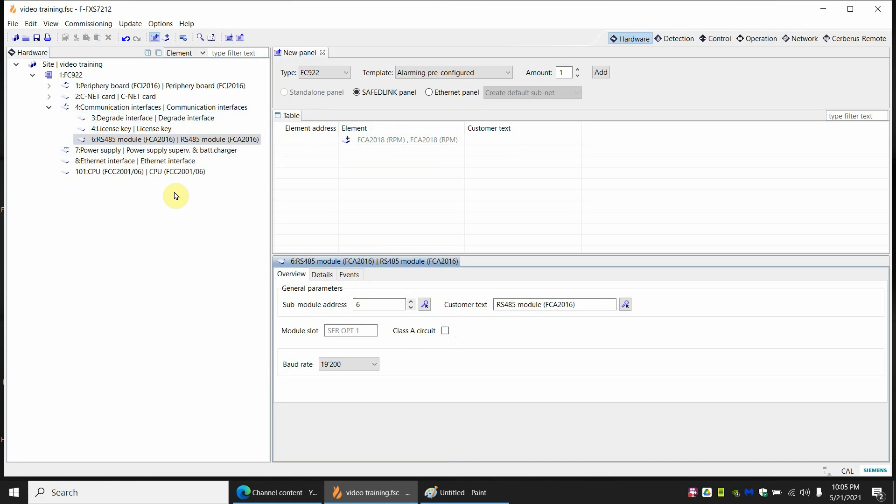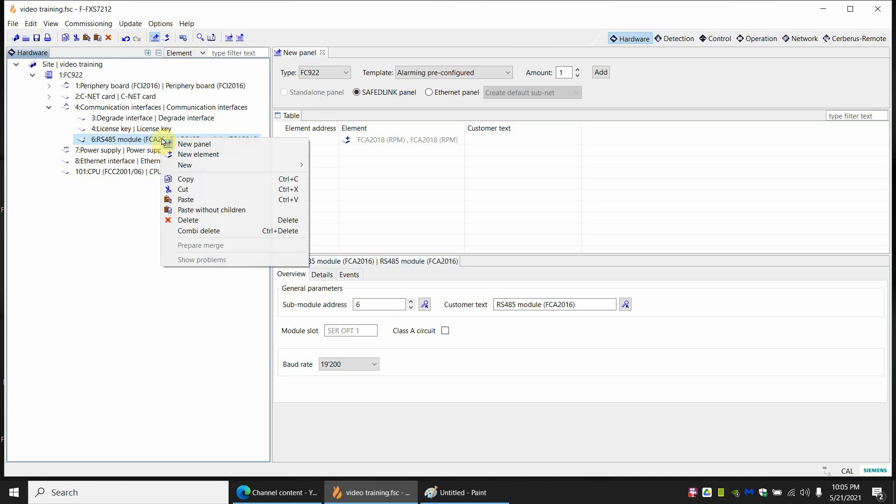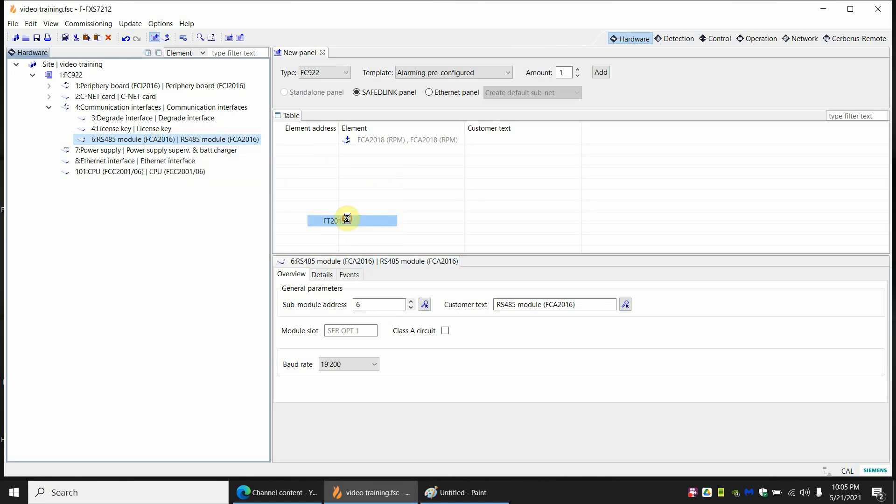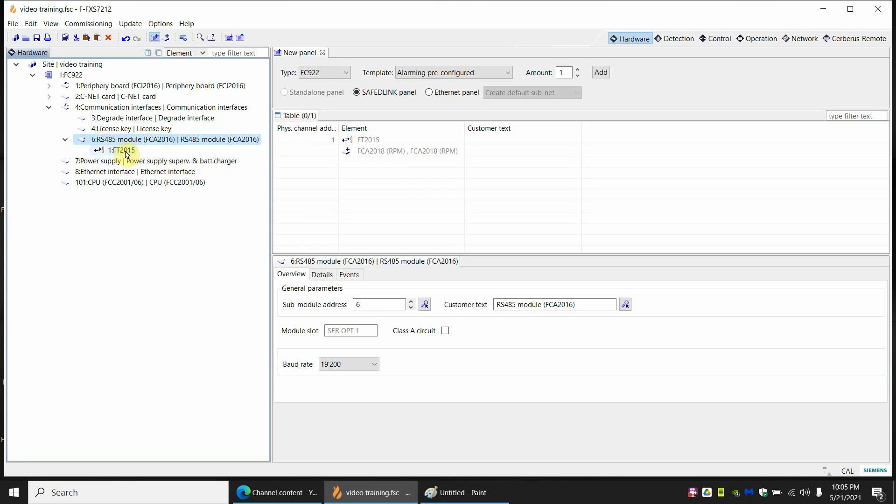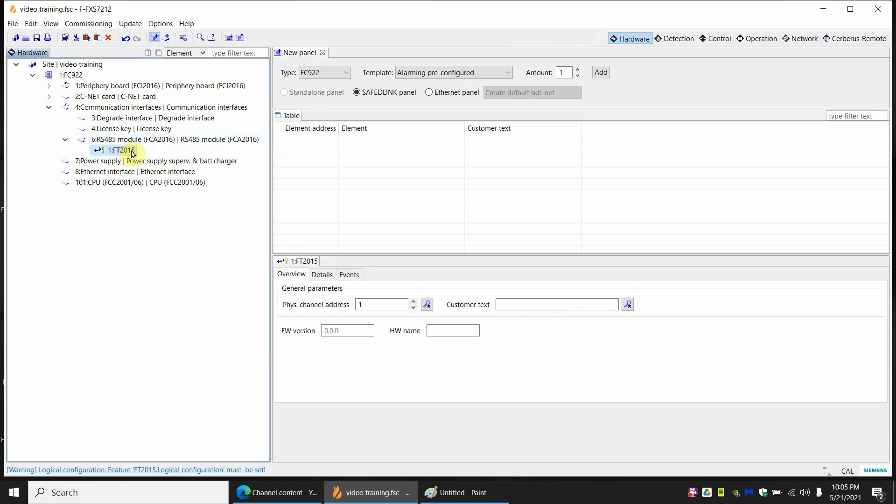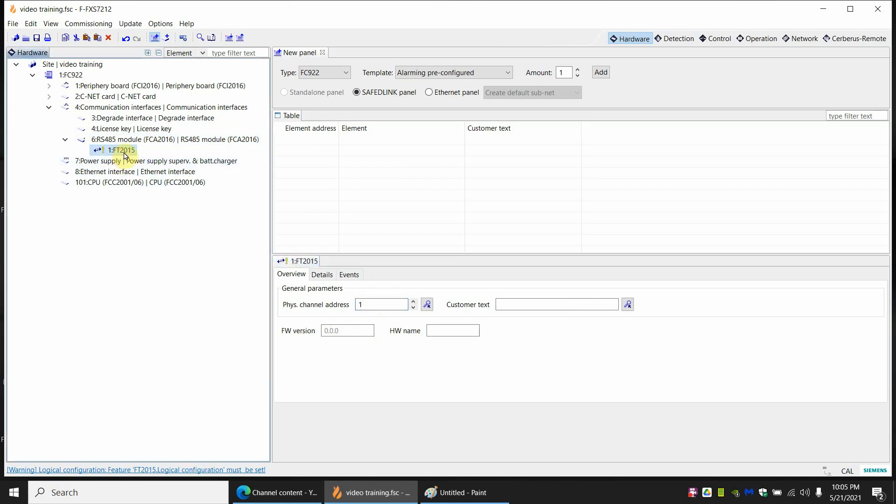After adding the RS-485 you have to add the annunciator. In this case I'm going to be adding in the FT-2015. So you're going to add that to the RS-485 by right-clicking. New. There it is. FT-2015. It assigns an address one. If you don't want the address one this is where you would change it. Right here. Address one is fine for me. But note we have the yellow exclamation point which means this is not going to show us anything at this point. We have not assigned this to do anything. So we have a device that has no function.